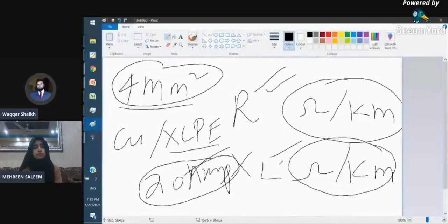And here, for whichever cable you want to give the manufacturer's input, like you have a 4 mm square cable and the manufacturer has given you 55 ampere ampacity, you just overwrite it over here with 55 ampere. In case of buried installation or conduit installation, for example, if the manufacturer is saying 40 amps, make it 40 amps. After you update the information for the 4 mm square cable, that is the ampacity part. As I told you, the first important thing is ampacity. Then resistance and reactance are the remaining things.